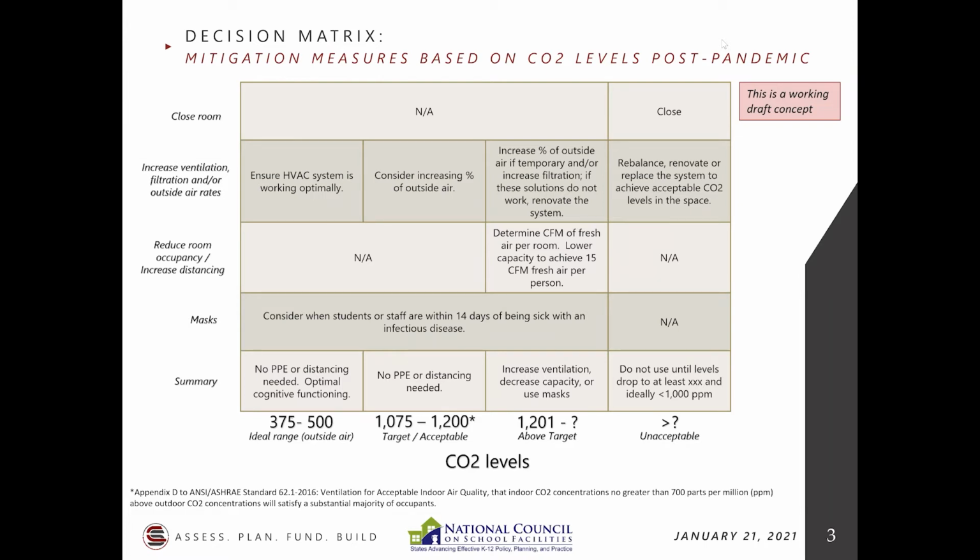When you look at CO2 levels indoors, it depends on what your levels are outdoors. In the past, you look at approximately whatever outdoors is, and you add 600 to 700 parts per million to that, and that is your acceptable level for indoor. That assumes you've got good calibration, that the instruments are reading properly. You have to take all these things into account, David. It's not as cut and dry as we'd like it to be.